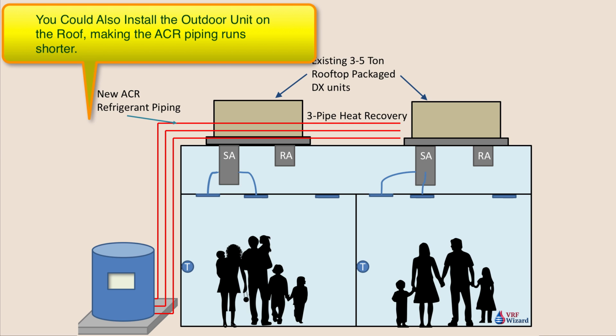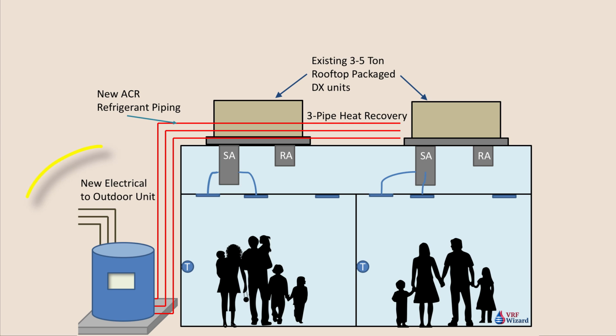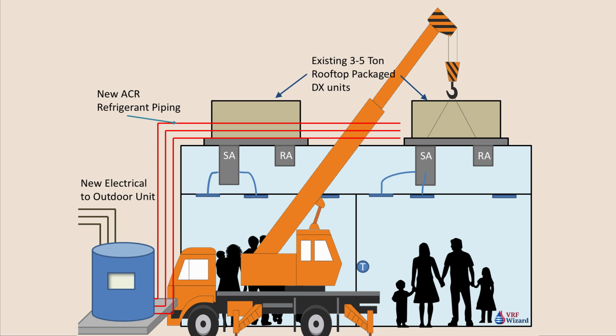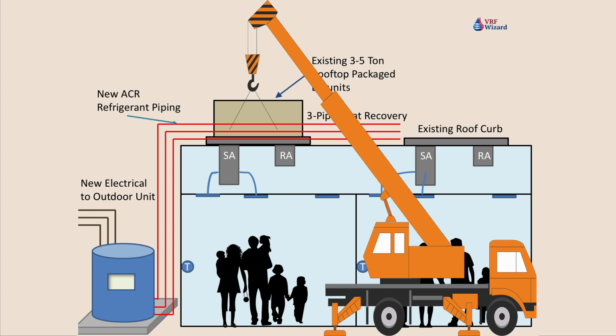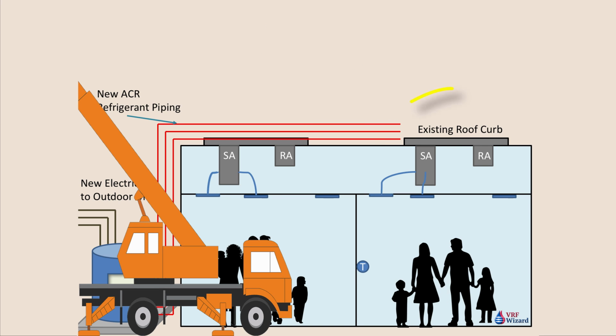This is for heat recovery, so we're running 3 pipes. And then you would run new electrical to the outdoor unit, get this all prepped and ready for the removal of those package units so your tenants can remain in the space as long as possible before you do the switchover.